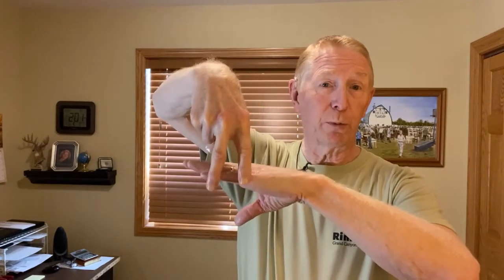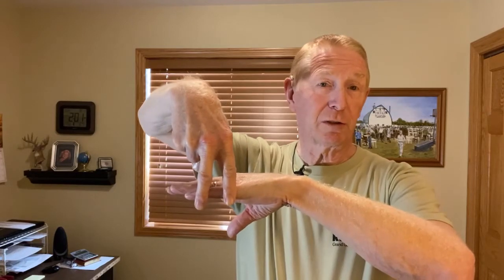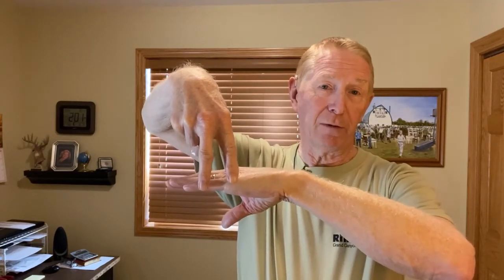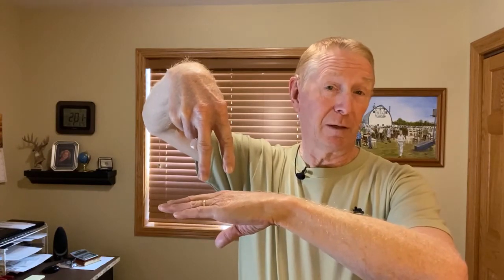Now there's several different types of low water fuel cutoff. One is the float type, where you have a hollow ball with air, and it goes up and down as the water fluctuates in the boiler, and it engages the switch. So if you have plenty of water in the boiler, the float goes up and it keeps the electric current going to the burner. The other type is a probe type. I could best describe that by just putting my two fingers down. So long as the probes are down in the water, it closes the circuit and keeps the burner running. If the water level drops out, then the circuit is opened between the probes and the burner will stop operating.